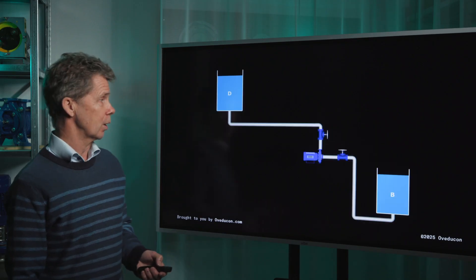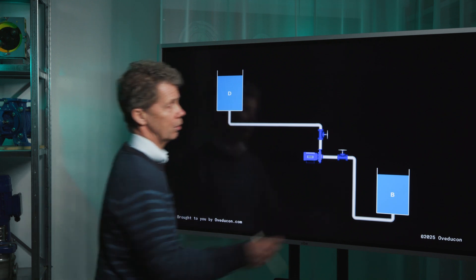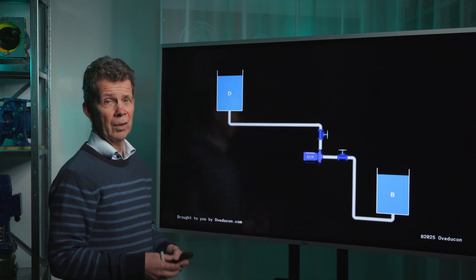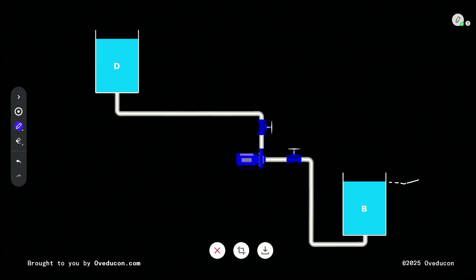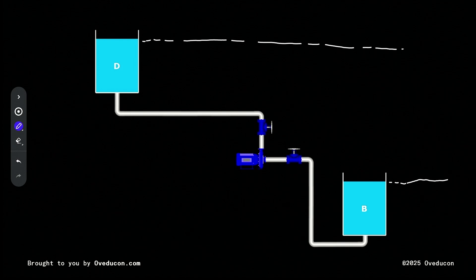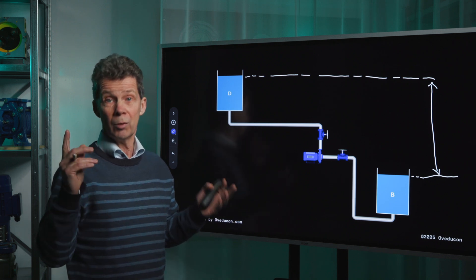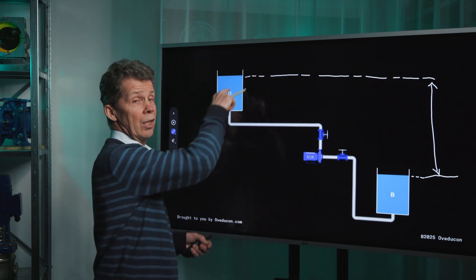In this drawing you see what we call a suction lift situation. The medium level in the suction tank is below the eye of the impeller. If we want to determine the static head for this situation, we draw a line from the medium level in the suction tank to the medium level in the discharge tank. This distance is called the static head for this situation, assuming the medium levels stay fixed.